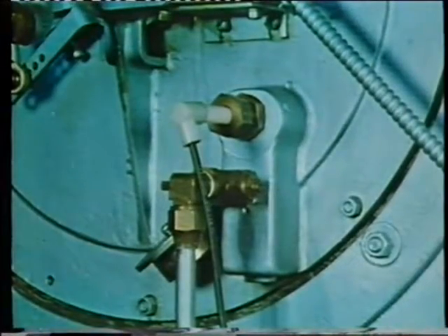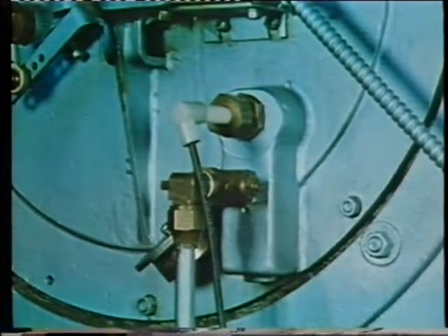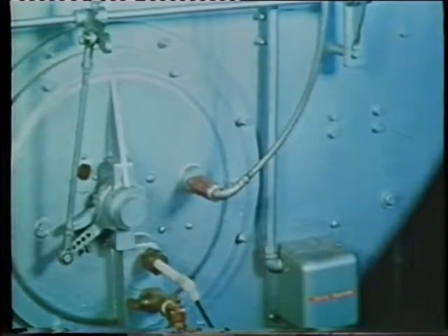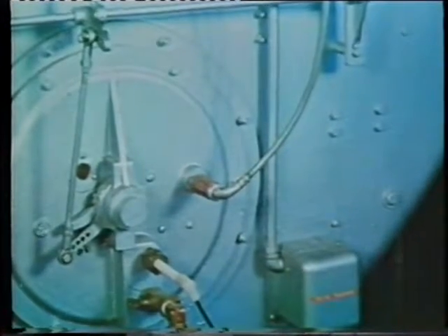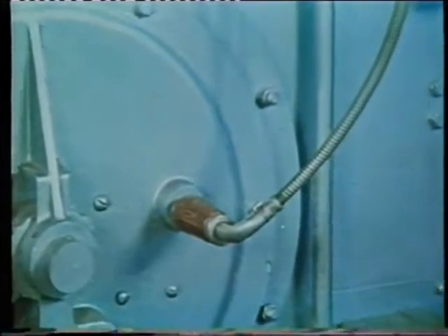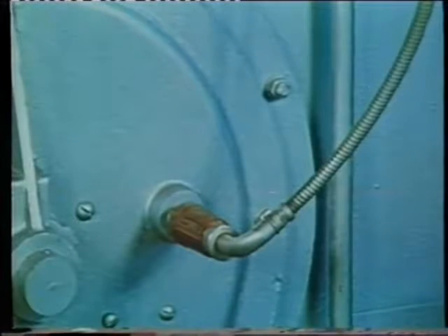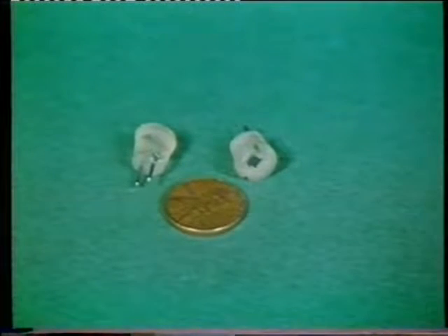At the same time, the ignition electrode provides the spark to ignite the gas pilot flame. If the flame scanner senses the pilot flame, the sequence continues. If not, the programmer will interrupt the sequence and shut the boiler down. The sensing device in the scanner may be a sulfide cell, an ultraviolet detector, or other type of apparatus.